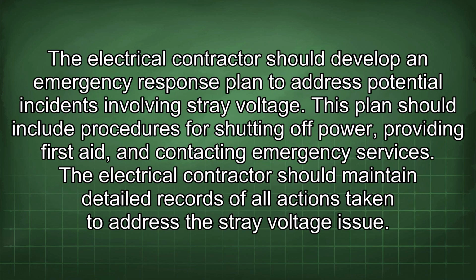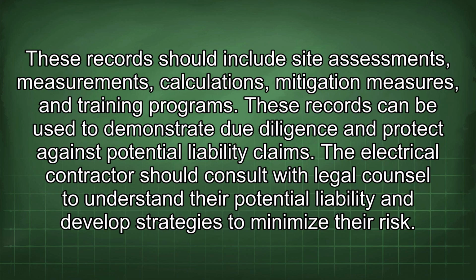The electrical contractor should develop an emergency response plan to address potential incidents involving stray voltage. This plan should include procedures for shutting off power, providing first aid, and contacting emergency services. The electrical contractor should maintain detailed records of all actions taken to address the stray voltage issue. These records should include site assessments, measurements, calculations, mitigation measures, and training programs. These records can be used to demonstrate due diligence and protect against potential liability claims.